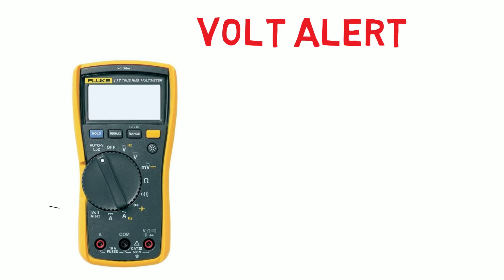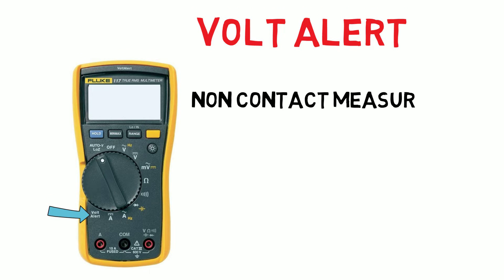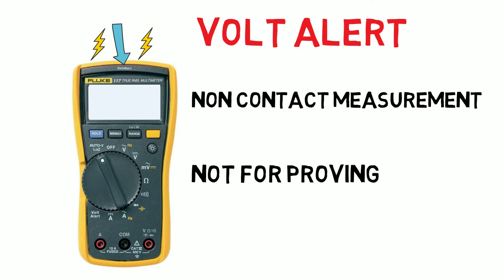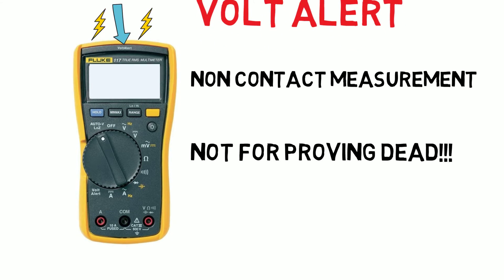Our last voltage measurement mode is the volt alert mode. In this mode the meter can detect AC voltage without the use of test leads — simply place the top of the meter near a live conductor. If a voltage is detected the meter will illuminate and a beeping sound will be present. Do not use this mode as proof there is no voltage, and always carry out a full test for dead with a proving unit before touching any conductor.